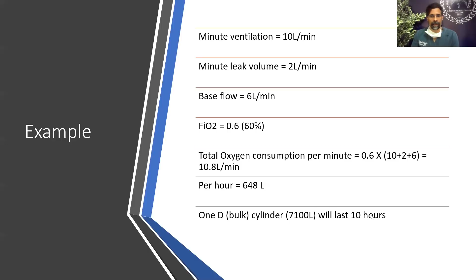That would depend on the type of ventilator. Some transport ventilators, for example, where the oxygen pressure itself drives the ventilator, will consume much more oxygen than what we calculated. Turbine-based ventilators, some of the newer models, do not use a compressed air source, and these ventilators tend to use a little bit more oxygen than what we calculate. A rough rule of thumb is to add 10 liters per minute to this calculation that we just did. The typical standard ventilators are the compressed gas ventilators, and they would usually go by this formula.